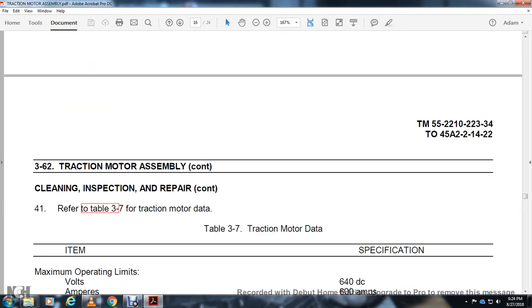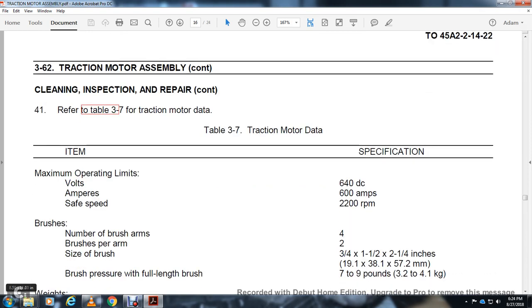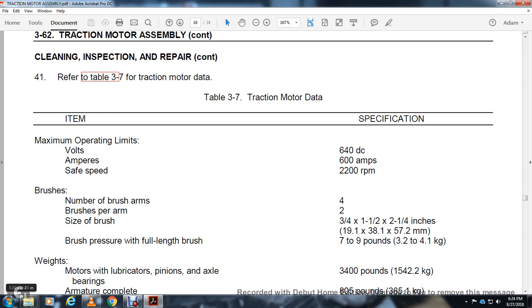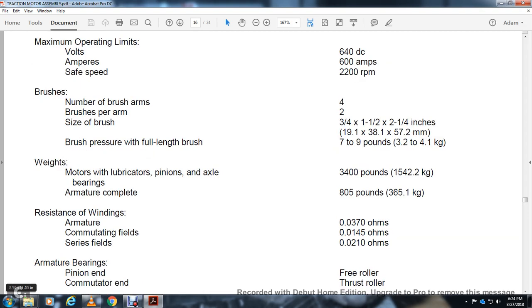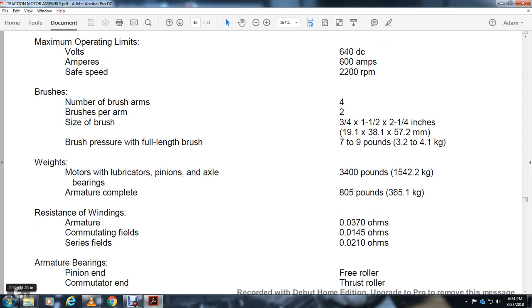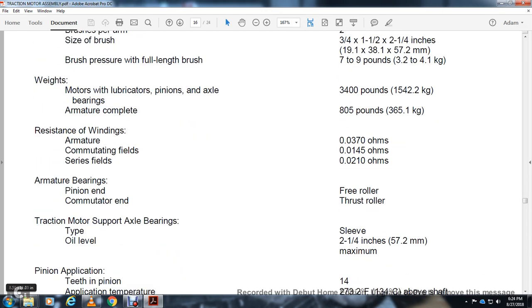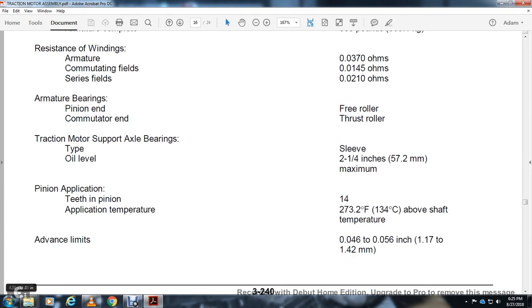Clean, inspection, and repair continued. Refer to Table 3-7 traction motor data. Maximum operating limits: 640 VDC, 600 amperes, safe speed 2200 RPM. Number of brush arms: 4, brushes per arm: 2. Brush size: 3/4 inch by 1-1/2 inch by 2-1/4 inch. Full length brush pressure: 7 to 9 pounds. Motor weight including lubricating pins and axle bearings: 3,400 pounds. Armature complete: 805 pounds. Resistance values — armature winding: 0.0370 ohms. Commutator fitting: 0.0145 ohms. Series: 0.0210 ohms. Armature bearings: pinion end free roller, commutator end thrust roller. Traction support axle bearing: sleeve type. Oil level: 2-1/4 inch maximum. Pinion application: 14 teeth. Application temperature: 273.2 degrees Fahrenheit above shaft temperature. Advance placement limits: 0.046 to 0.056 inch.